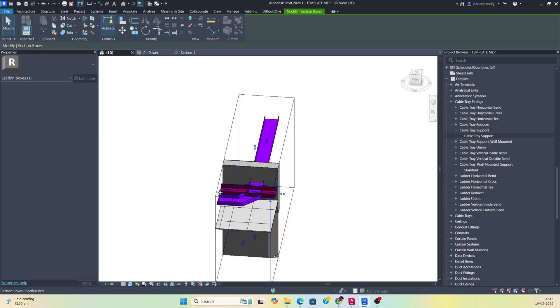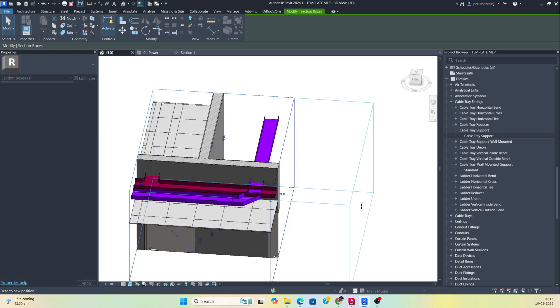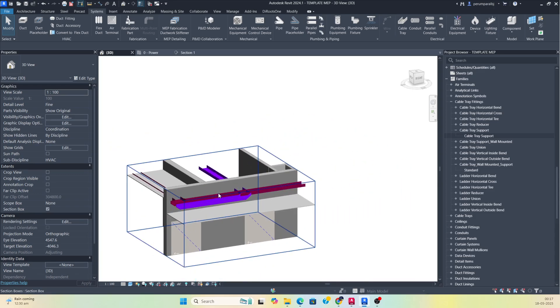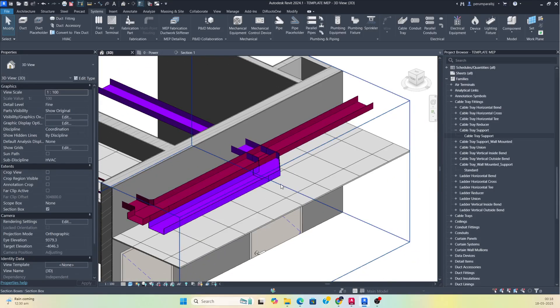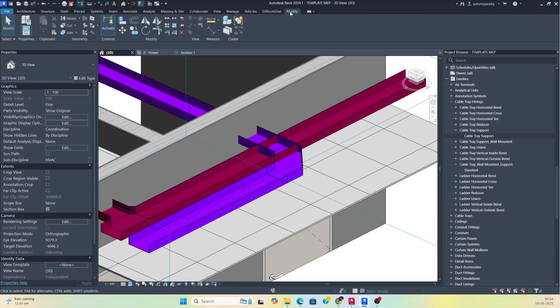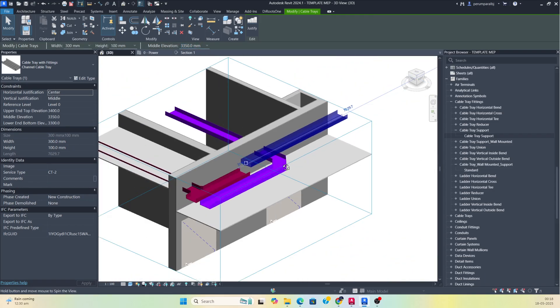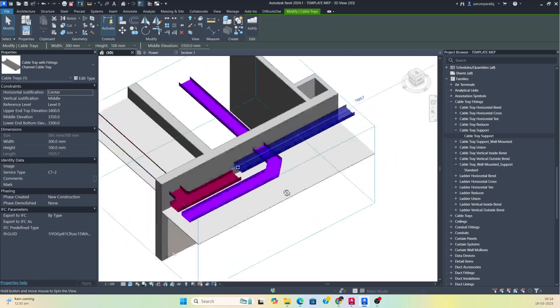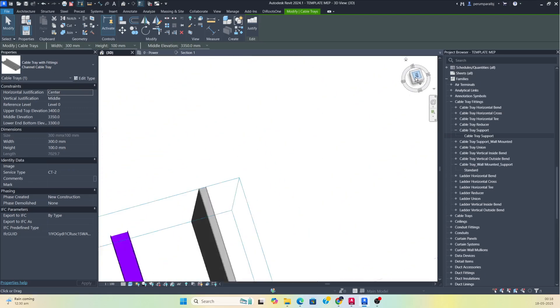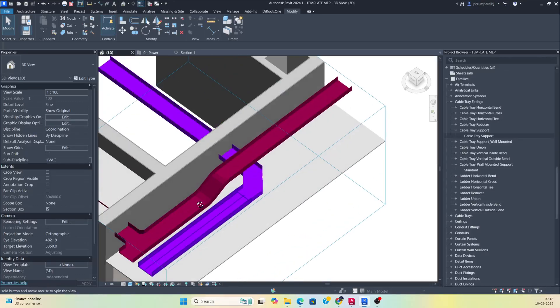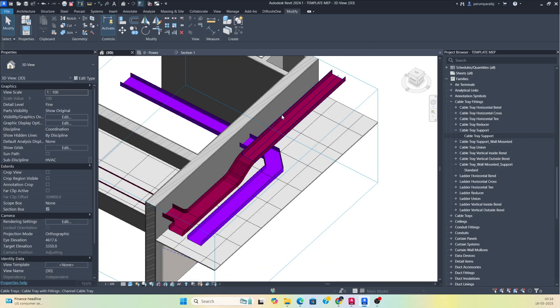To resolve the clash, you can move one cable tray up or pick whichever one you prefer to raise. Go to Modify, use the Split tool to split at the gap — split over here. Then change the elevation of this cable tray segment to 3350 so it goes up. You can see the clash is gone. Then use the Join tool to connect it — a bend will automatically be created. Like that you can arrange ceiling coordinations and MEP service coordinations.